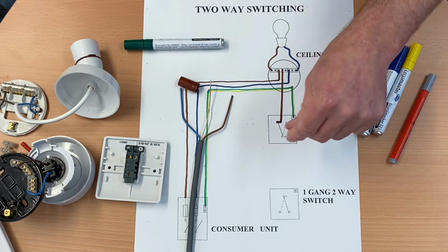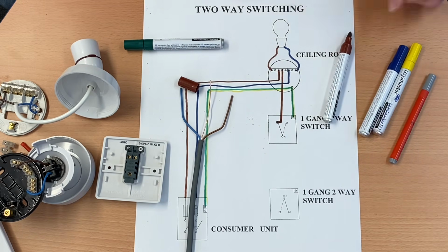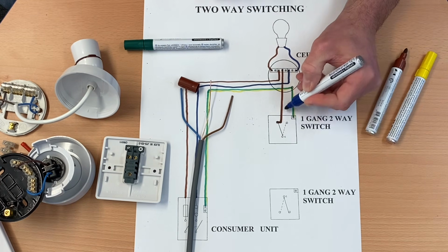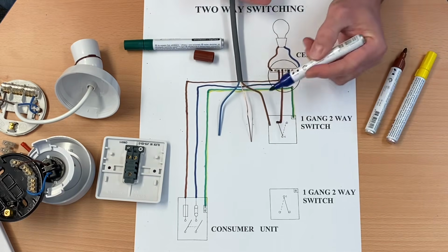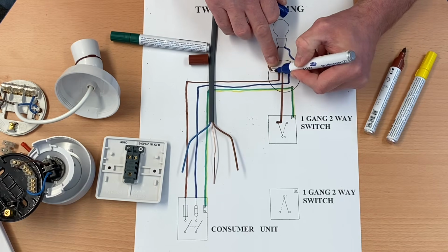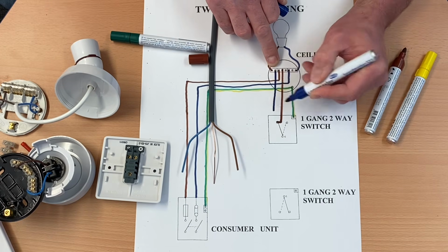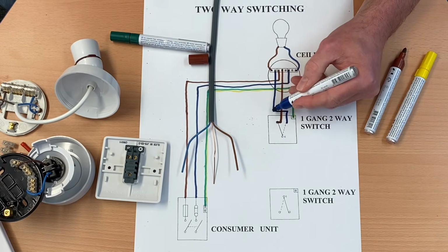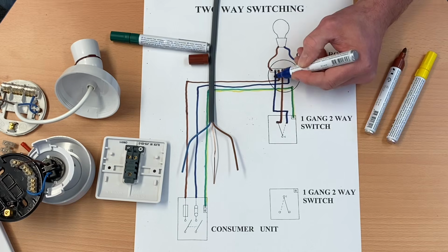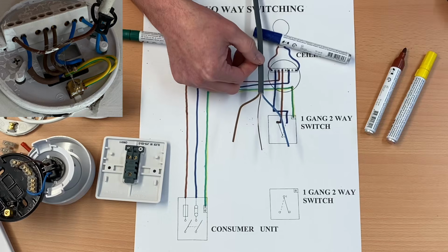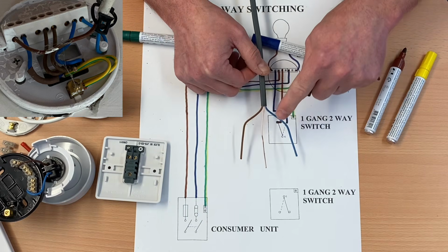We said, didn't we, that the next bit you've got to be really careful of because this is not a neutral. This one here is not a neutral. So I'm going to bring this one, which is blue, coming down to the switch, is actually my switching line. So I'm going to need to bring that down correctly. So my switching line comes out of here, like so. So I can bring that down there. And I can bring it across and into there. I could have had these 2 the other way around, doesn't matter. It's just showing the cables coming down, permanent line comes down, and not a neutral. We looked at it before, we said it was switching line. So this cable comes down here to the switch with permanent line, CPC and switching line.